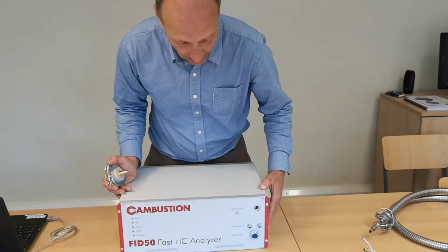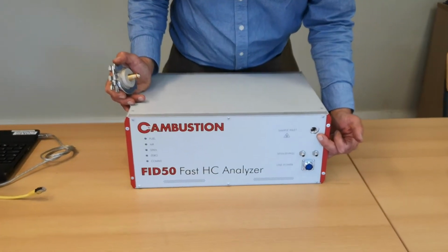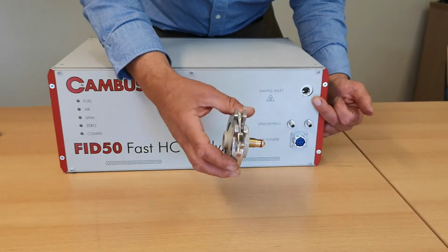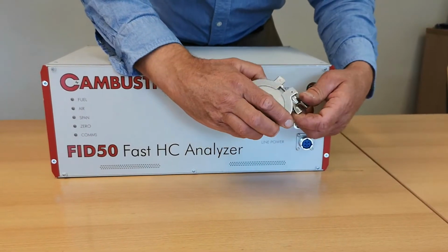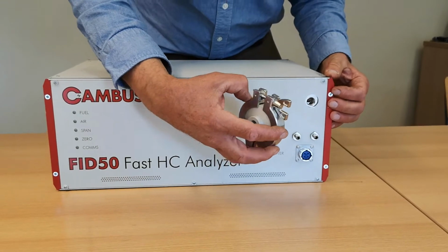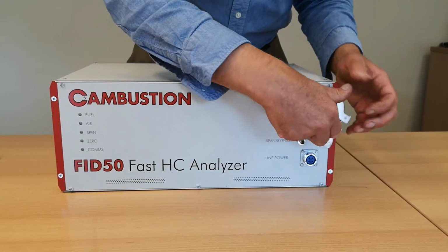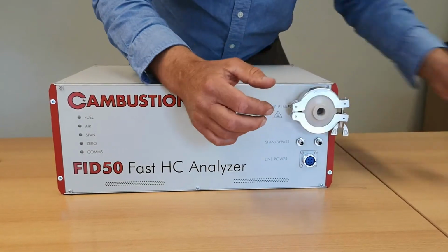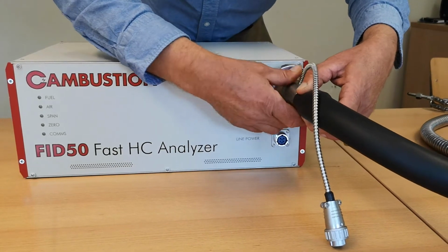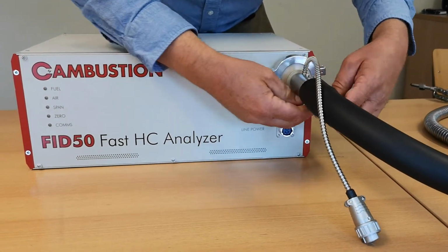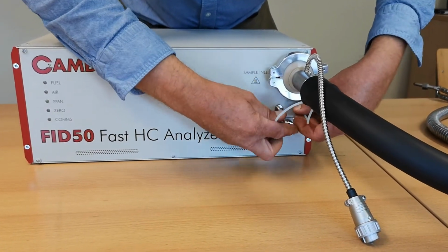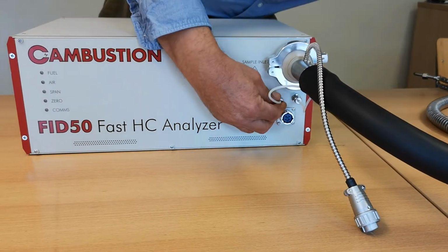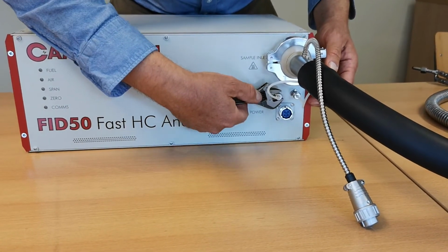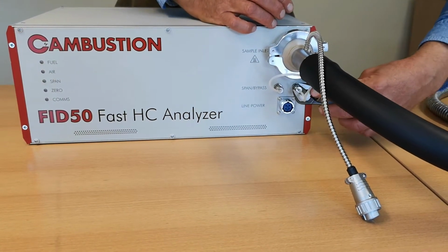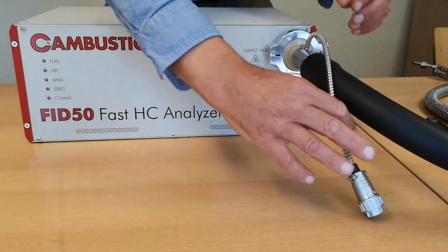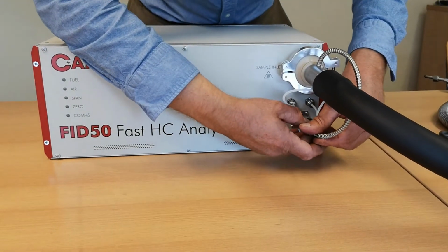The connections on the front panel are basically confined to the connections for the heated sample line. There's also this optional sample filter though, and I'll show you how to take this apart and change the filter paper in here in a separate section. But if we screw in the sample filter first, then the heated sample line screws into the filter like that. There are two pipes which need to be attached at these fittings and very gently tightened up just slightly. And finally, there is the electrical connector which provides the power for the heated line.